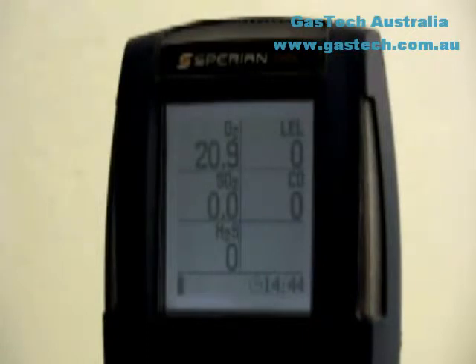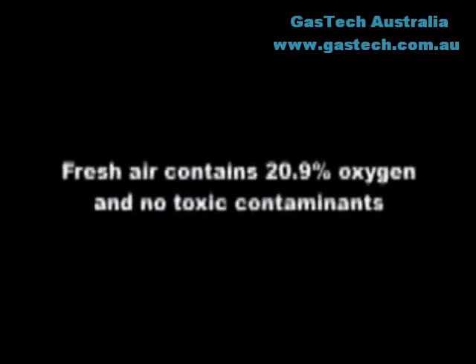Check the readings for fresh air. The oxygen reading should be 20.9%. Toxic and LEL sensors should read 0 ppm. If the instrument shows other readings, it should be fresh air 0 calibrated before proceeding with the bump test.